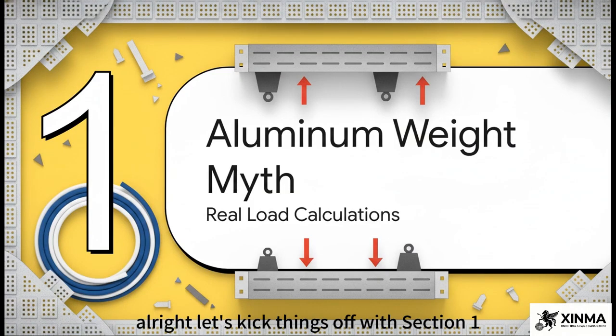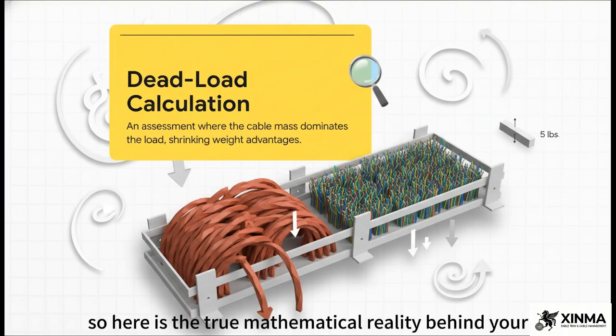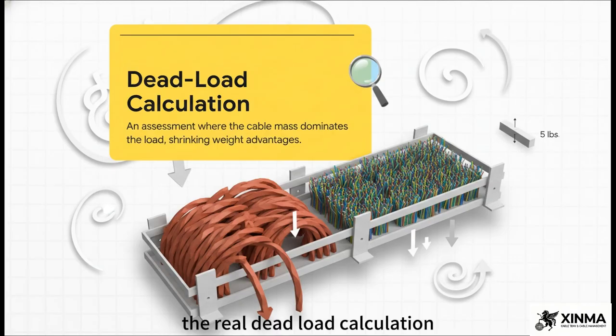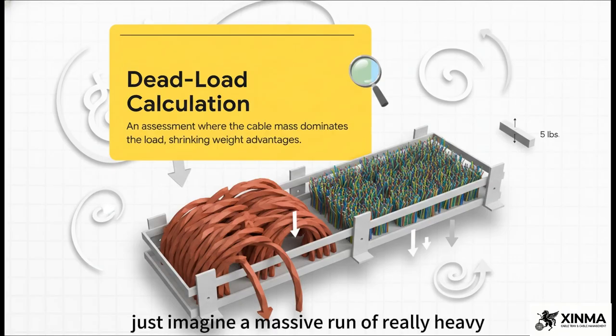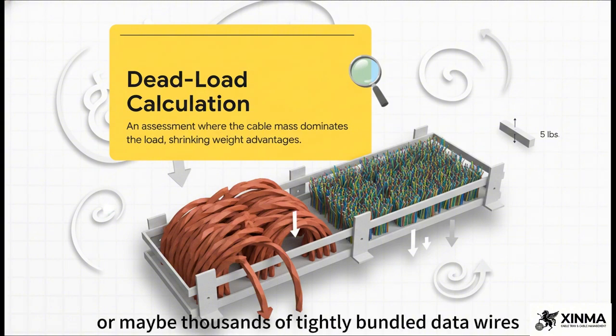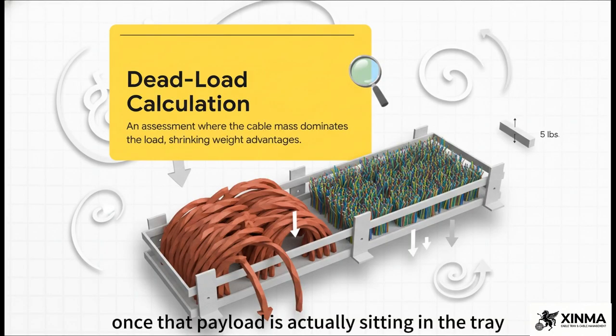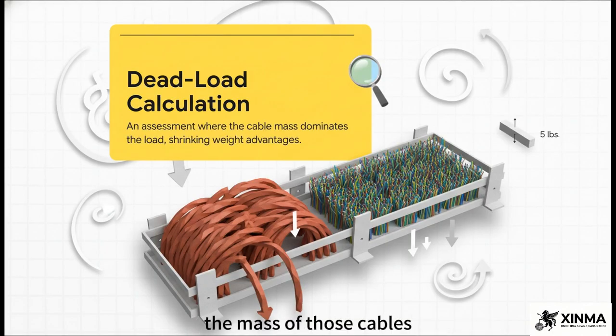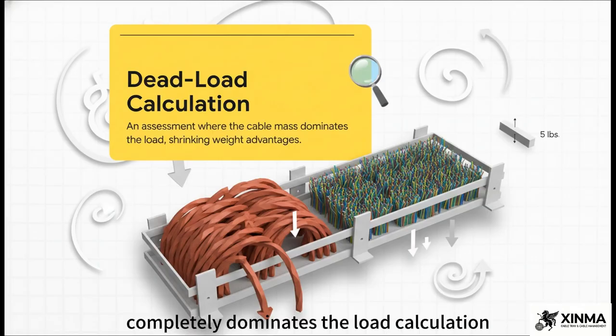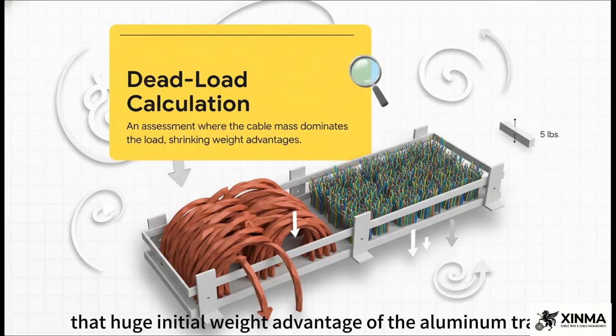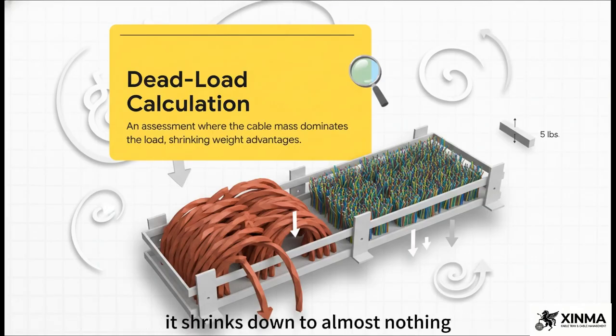Let's kick things off with Section 1, the aluminum weight myth. Here is the true mathematical reality behind your spec, the real dead load calculation. Imagine a massive run of heavy, thick copper power cables, or thousands of tightly bundled data wires. Once that payload is actually sitting in the tray, the mass of those cables completely dominates the load calculation. That huge initial weight advantage of the aluminum tray shrinks down to almost nothing.